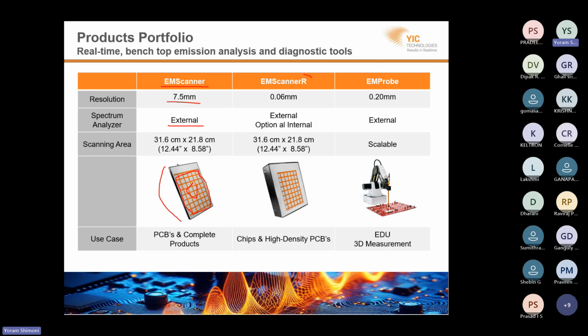The next version is the R version. R stands for high resolution, and the maximum resolution of that unit is 0.06 millimeters, so it's less than a human hair, essentially. The scanning area is the same scanning area, and we're using an external spectrum analyzer. The key difference between the EM scanner and the R version is that the R version is designed for smaller DUTs, even though the scan area is the same, but scanning the entire area at 0.06 millimeters will probably take a few hours.